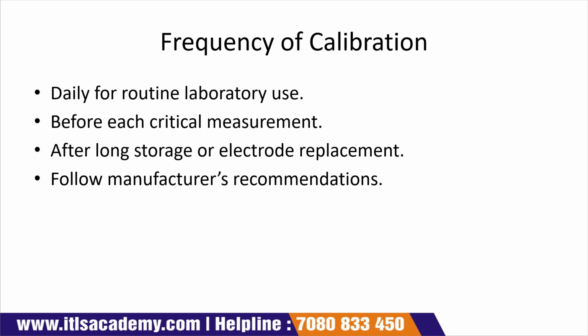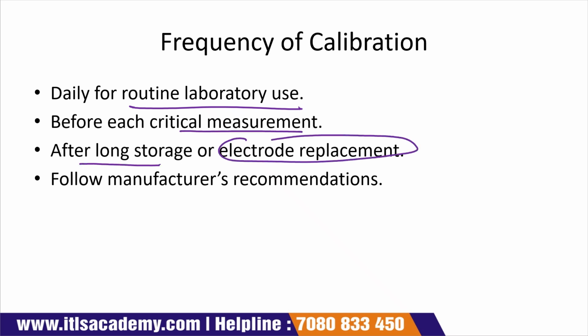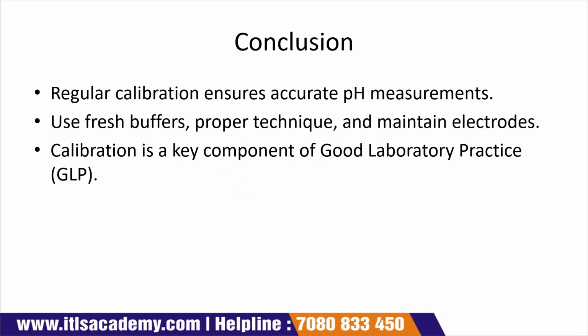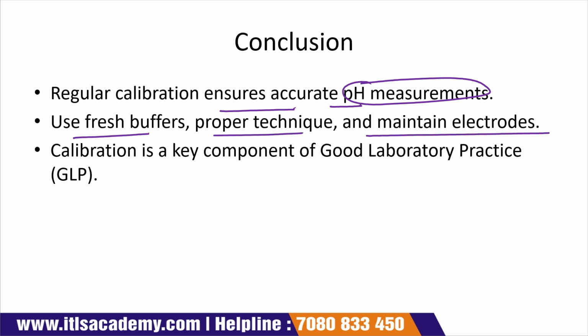Frequency of calibration: daily for routine laboratory use. You have to calibrate your pH meter daily, or when you start your work, before each critical measurement, after long storage or electrode replacement. Follow the manufacturer's recommendations. Conclusion: regular calibration ensures accurate pH measurement. Use fresh buffer, proper technique, and maintain the electrode. Calibration is a key component of good laboratory practice. So this is all about the calibration of the pH meter.